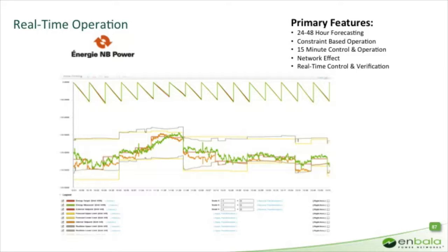That sawtooth at the top is the actual energy forecast delivered to us that all of our loads need to burn through in a 15-minute period. The red line, which you can barely see, is the signal delivered to us by New Brunswick. They basically say, get to this endpoint every 15 minutes. On an energy basis, we're actually optimizing for that every 4 seconds.